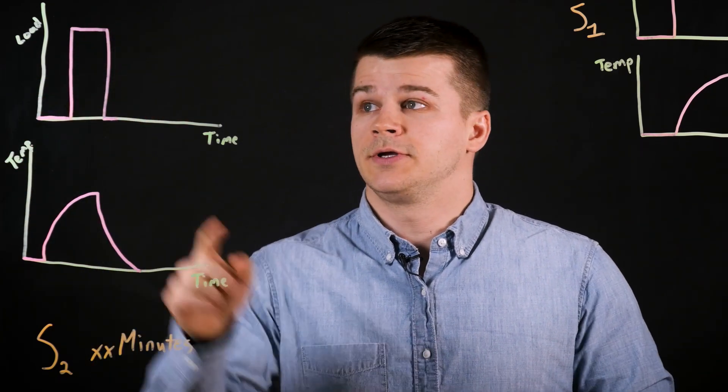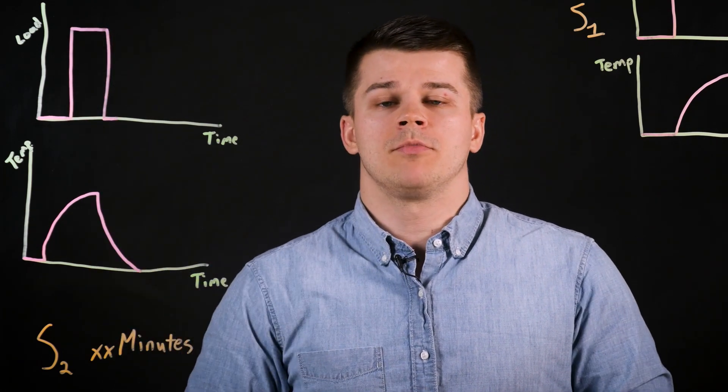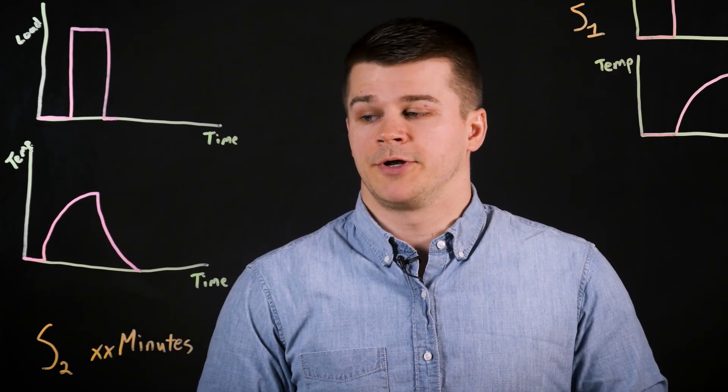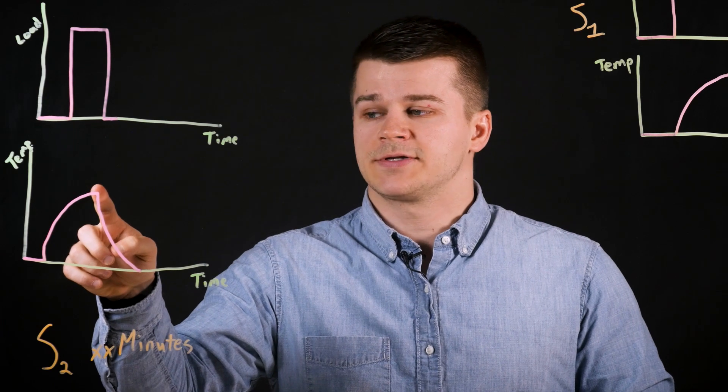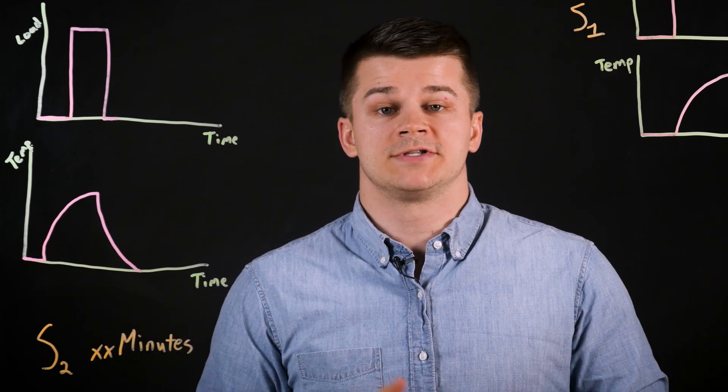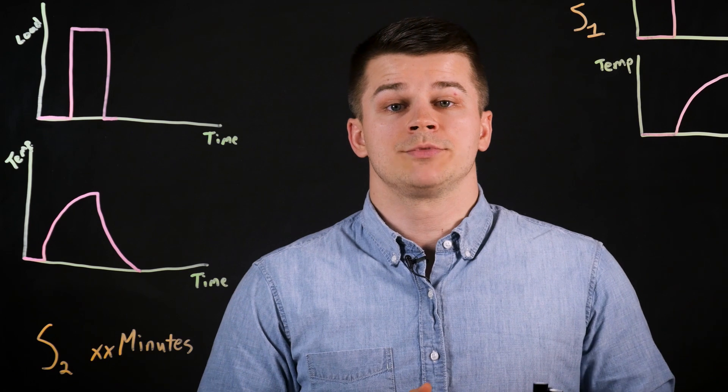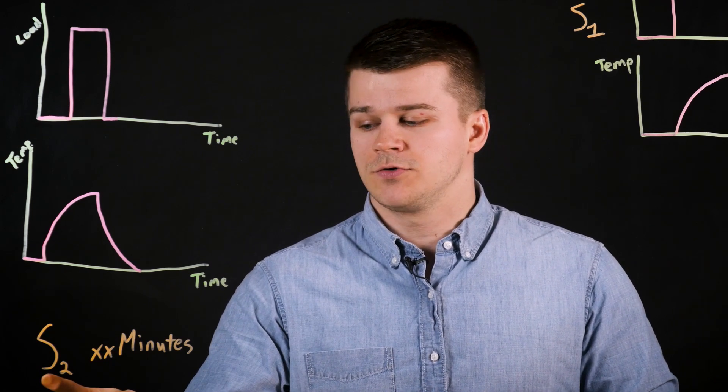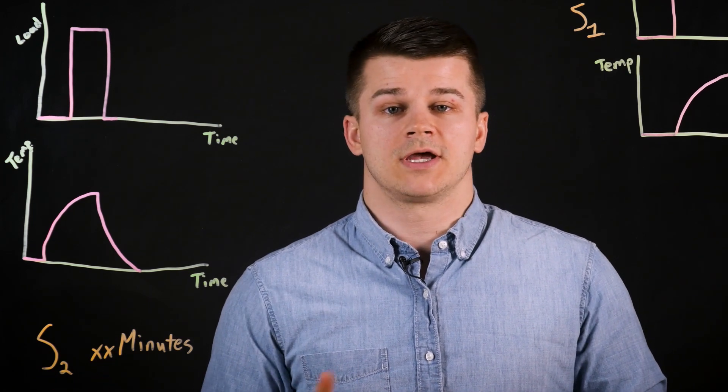Unlike continuous duty, the load is removed before the motor is allowed to reach its thermal equilibrium. At this point, the motor rests and is allowed to cool down until it reaches the ambient temperature of the environment. The short-term duty cycle is abbreviated as S2 followed by the number of minutes in the cycle.